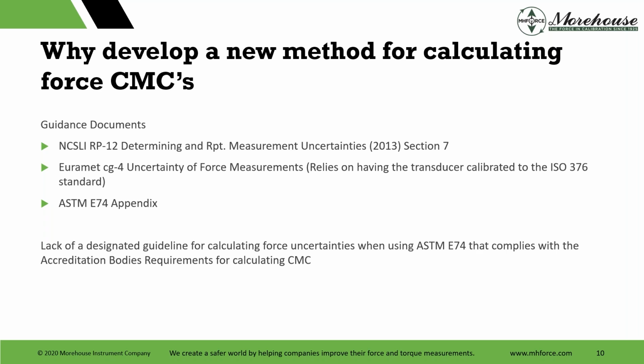that. Euramet cg-4, some people may say, yeah, that's Europe. They use a bit different method, and it relies on having the transducer calibrated to ISO 376. And I know we have some people on this webinar, hopefully some know what ISO 376 is. It's basically the European standard, not equivalent to E74, but kind of is. You need to calibrate to ISO 376 to perform calibrations to ISO 7500. ASTM E74 is similar in that you do calibrations to E74 here to calibrate to ASTM E4. Though the standards are different, so they're not really equivalent. It's just about the same, and there's a lot more to the ISO 376 standard.